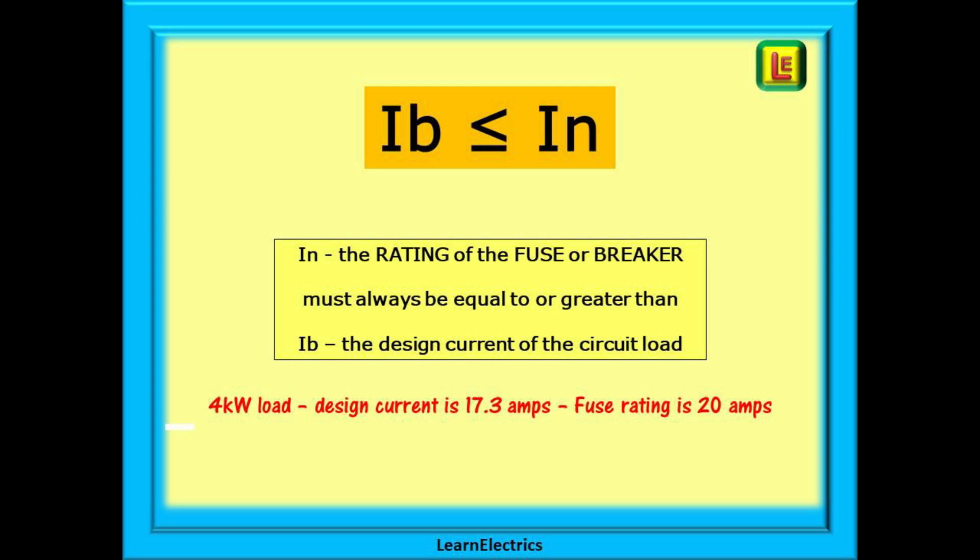IB must not be more than IN. Or another way, IN, the rating of the fuse or breaker, must always be equal to or greater than IB, the design current of the circuit load. A 4kW load has a design current of 17.3 amps, and we will need a 20 amp fuse or circuit breaker.